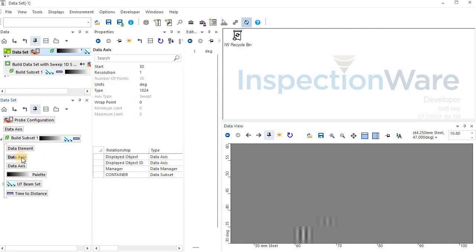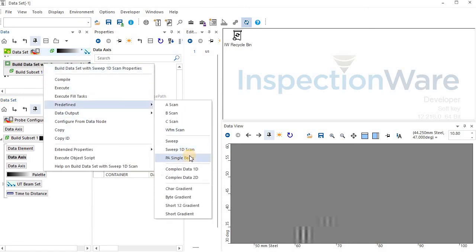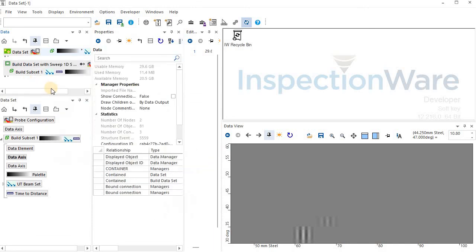And so you've got your three axes here. The waveform axis, the A-scan axis, is that one. The sweep axis, that's going across, recording for each waveform. And then this one records each scan position. I think that's a good representation. This is the same thing with complex data, so I don't think that gets us any further.